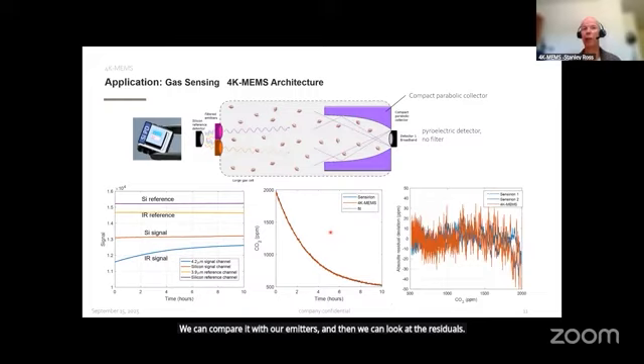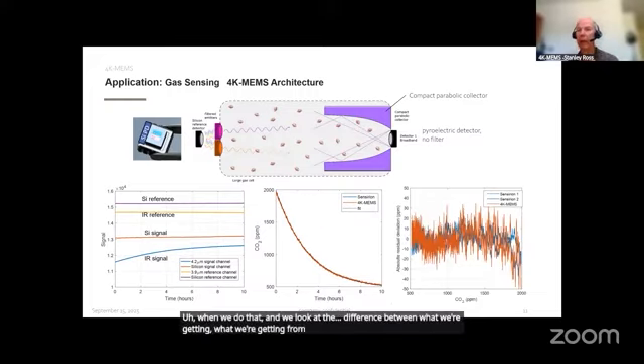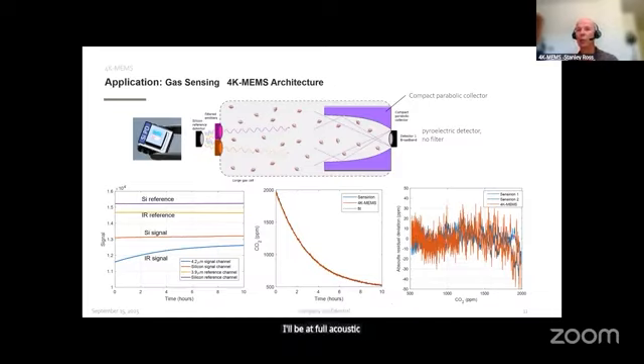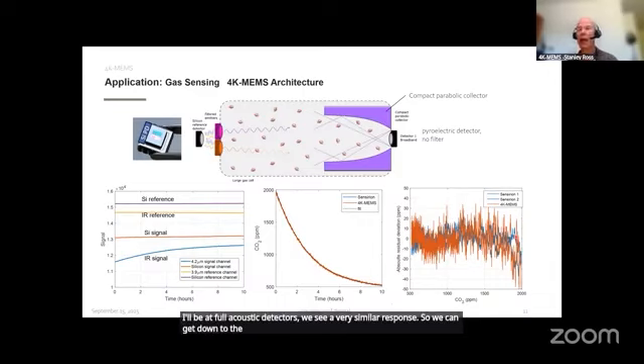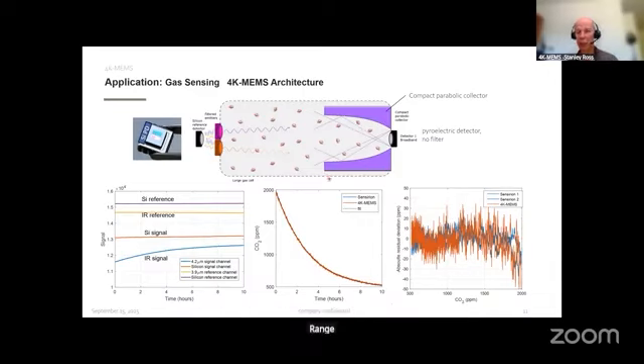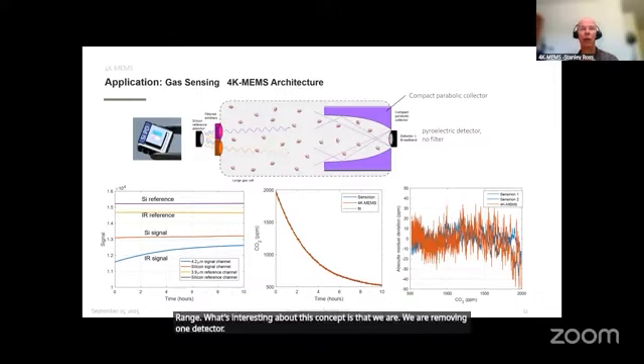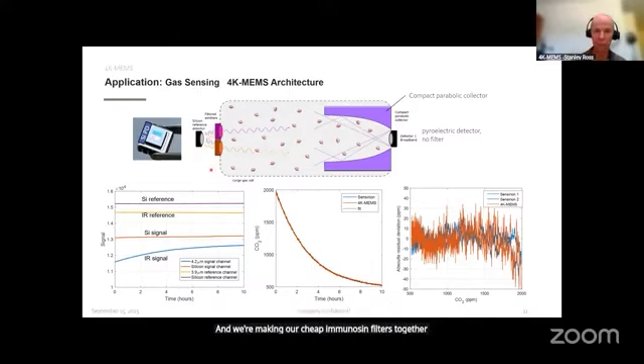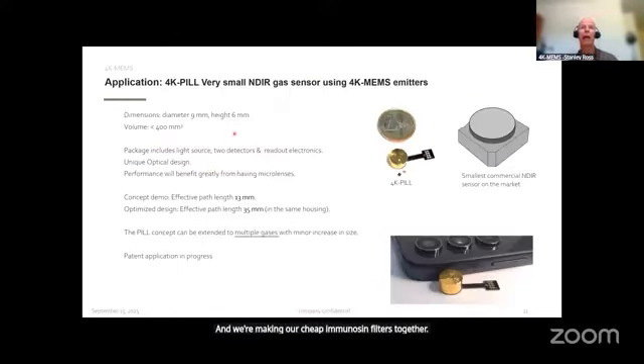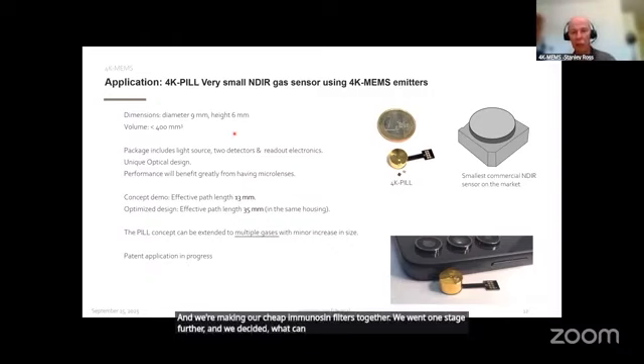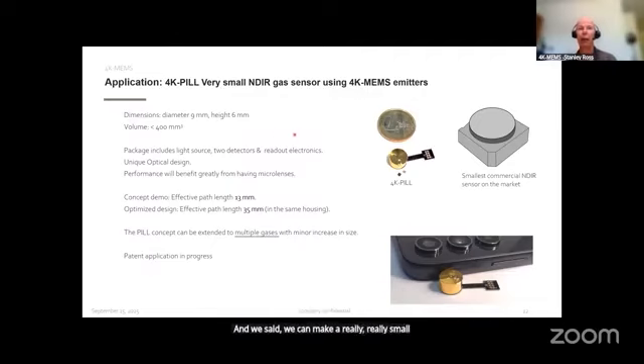And when we do that and we look at the difference between what we're getting from the Sensirion, albeit photoacoustic detectors, we see a very similar response. So we can get down to the 10 to 20 ppm range. What's interesting about this concept is that we are removing one detector and we're making our cheap emitters and filters together. We went one stage further. We decided, what can we do with a really, really small emitter? And we said we can make a really, really small NDIR gas sensor.